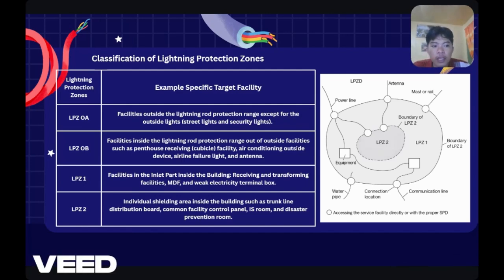So protecting electrical and electronic systems from the impacts of lightning is the primary objective of the lightning protection zone. As it passes through various zones, it gradually lowers electromagnetic interference and surge voltage. This guarantees dependable system performance and helps shield delicate equipment from harm. In general, it manages lightning energy and securely disperses it before it reaches vital devices.